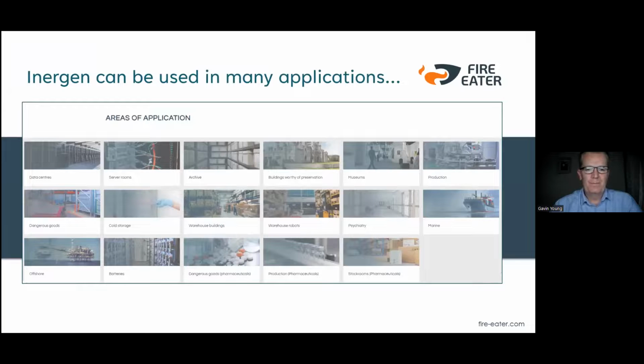Areas of application. Well, the normal areas of application would be data centers or server rooms. Typically, that's where you would think, or switch rooms, for example. But more and more, it's changing. We do have a far reach from Ireland to the likes of the United States and the Middle East, where water is a problem, in the likes of Arizona, for example. So there's a lot of systems going in there into meat factories, office blocks. So it doesn't necessarily have to be the typical data center or server rooms. You can put an Inergen system into pretty much anywhere as long as you've got an enclosed space.